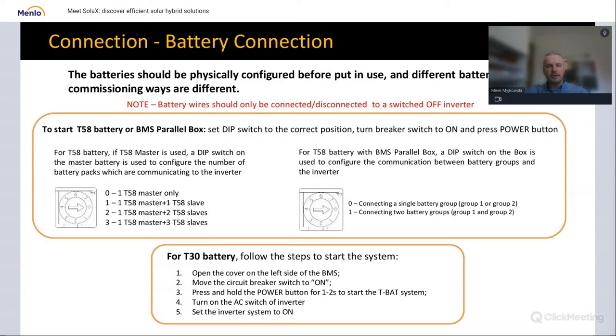Of course, when you're connecting anything from the battery side to the inverter, it should be switched off. Don't risk electric shock by trying to connect the battery into the working inverter, or turning on a battery that is already connected to the working inverter. That is not a good idea, absolutely.